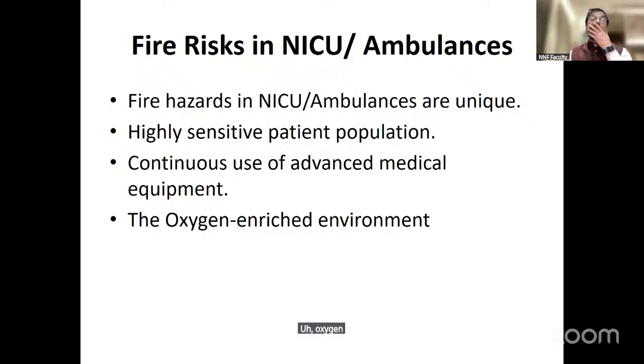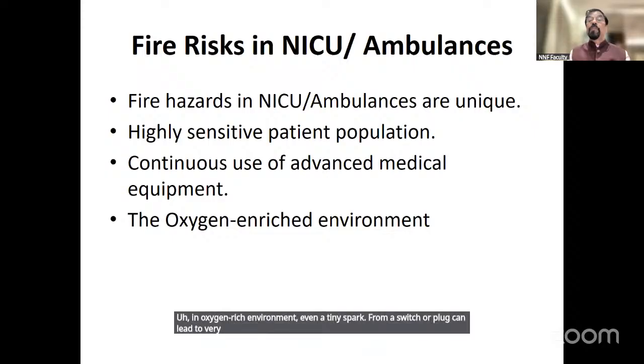Oxygen enriched environment is the major risk factor. In an ICU, oxygen leaks from cylinders, oxygen concentrators, pipeline joints, flow meters, and mishandling of cylinders, like falling of cylinders, damaged valves, or improper storage, can lead to sudden leaks. In an oxygen-rich environment, even a tiny spark from a switch or plug can cause very rapid fire spread.